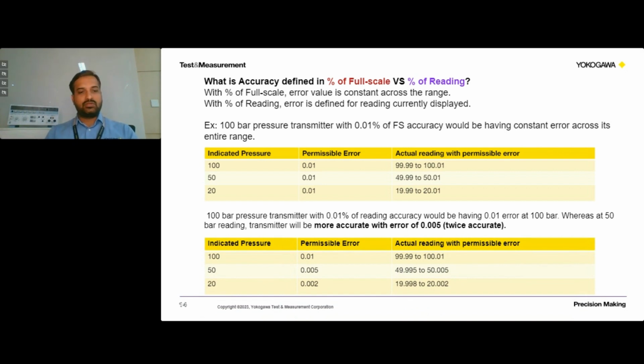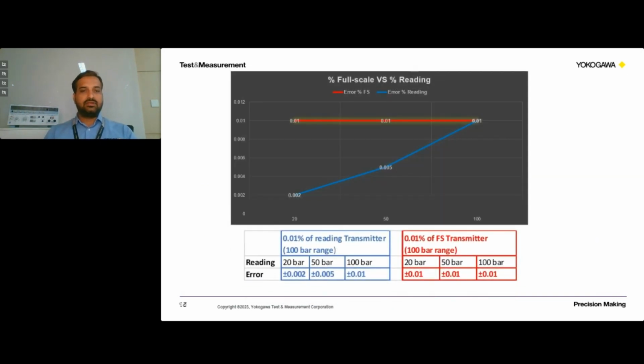At 100 bar range, we have 0.01 as the permissible error. When it comes to 50 bar, you can see the range of reading with a permissible error has improved. So instead of 49.99 with the percentage of full scale error, here we have a better value, which goes further to the third decimal point. In this graph, it is clearly shown how percentage of reading and percentage of full scale make a difference to our values or readings. As you can see, this red line indicates the constant error with percentage of full scale, whereas this blue line indicates percentage of reading accuracy. Here you can see in the lower range we have lesser error and better readings, whereas with percentage of full scale it is constant across the range.